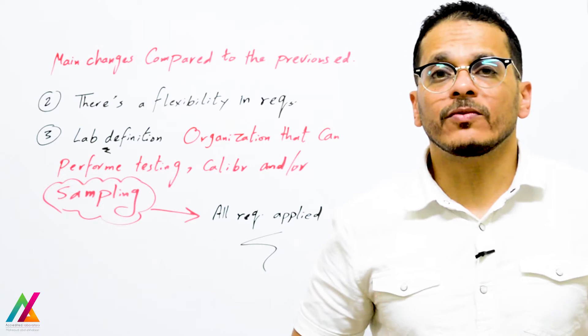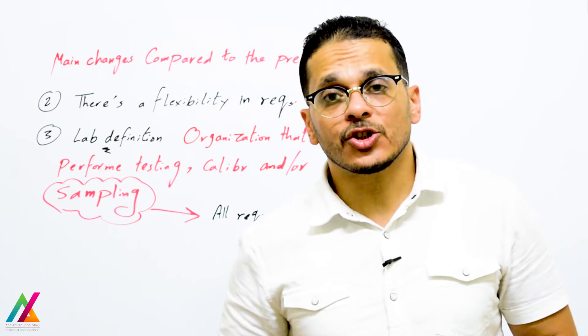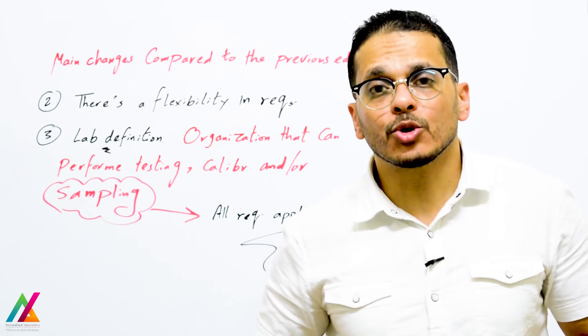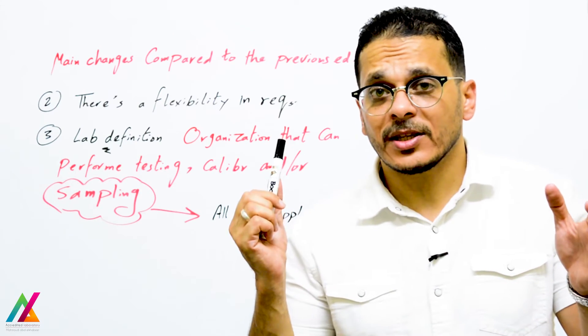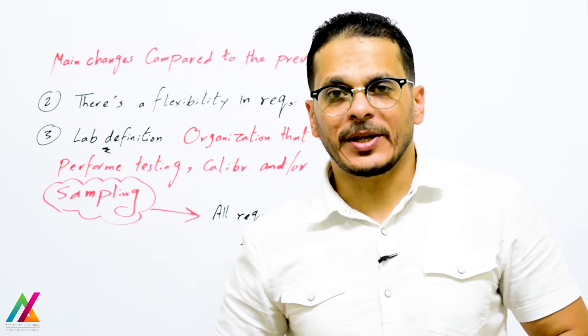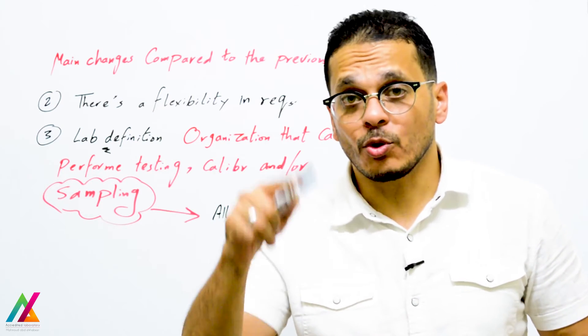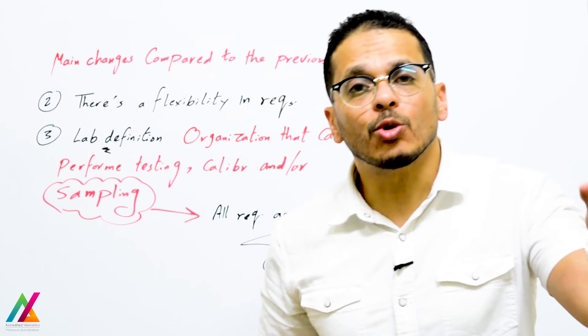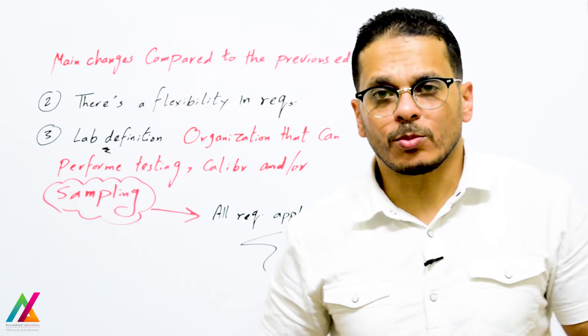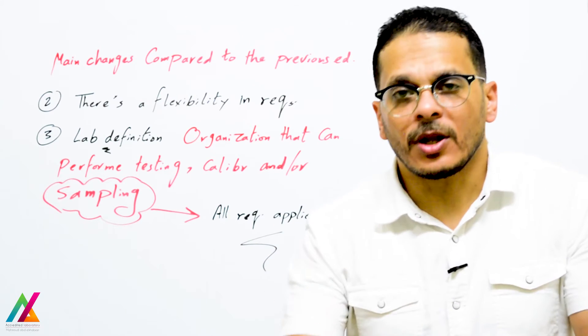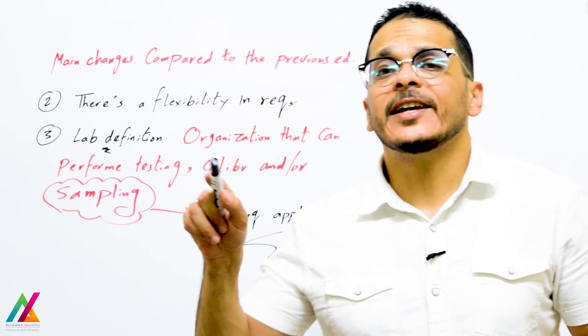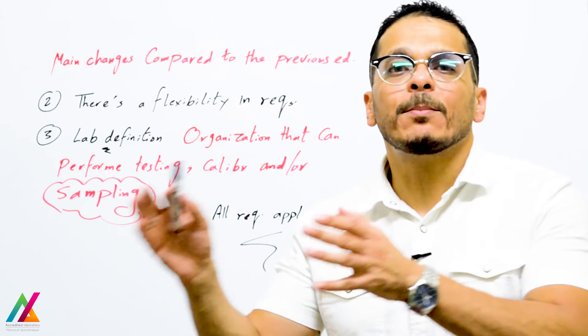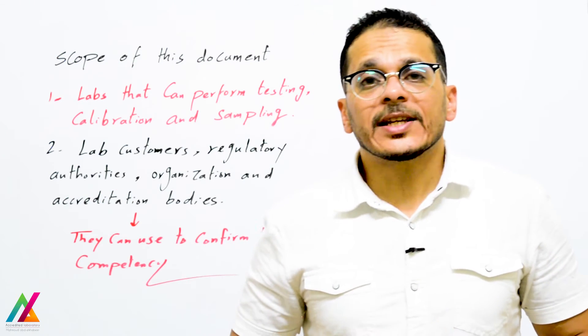Another point added to this edition is the definition of laboratory. A laboratory is now defined as an organization that can perform testing, calibration, and/or sampling. If the lab is responsible for sampling, they shall apply all requirements of this document to sampling as well — including measurement uncertainty, method validation, and everything applied to testing and calibration. If the lab is not responsible for sampling, they do not need to apply sampling requirements, but in the final report they shall state that the lab is not responsible for sampling and that analysis is based on the sample received from the customer.